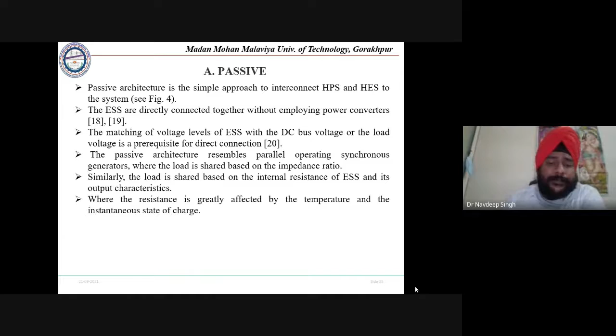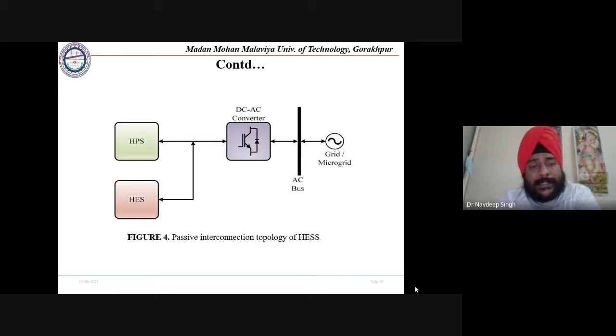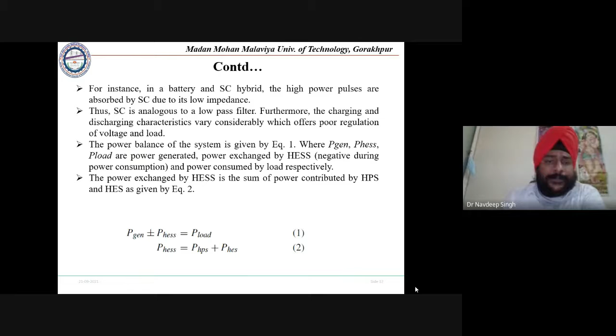Next is the passive interconnection topology. The HPS and HES are directly connected, but this DC supply is connected to a DC to AC converter. What is the difference here? Normally we provide an AC voltage through a DC to AC converter, so why do we still call it passive while using a DC to AC converter? Normally we say so because the HPS and HES are directly connected. They are not connected through an inverter or DC to DC converter. If we use another connection, we will call it an active connection, but that is not the case here.